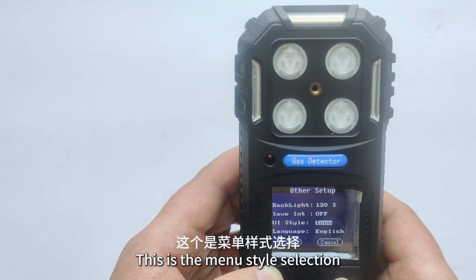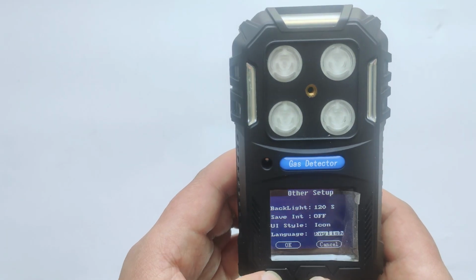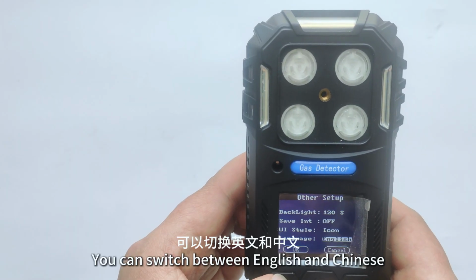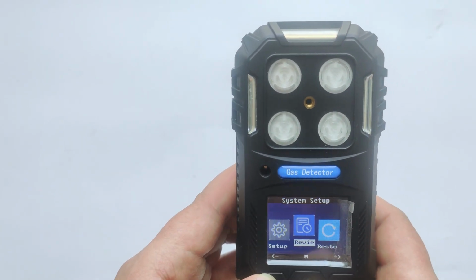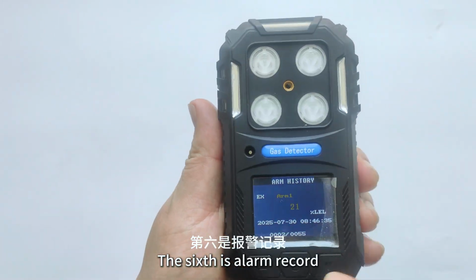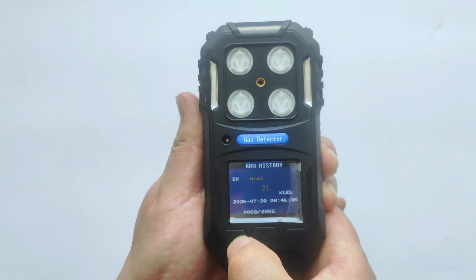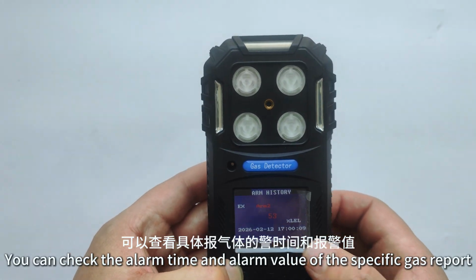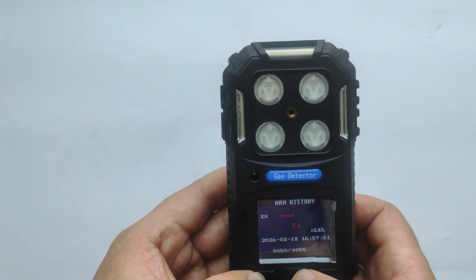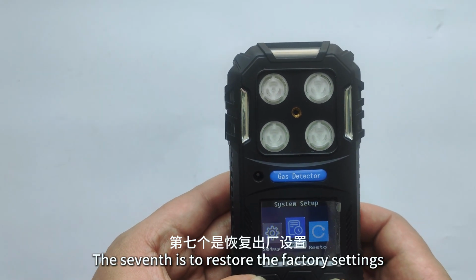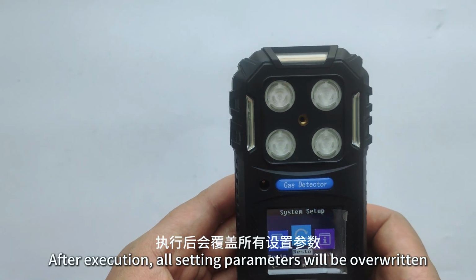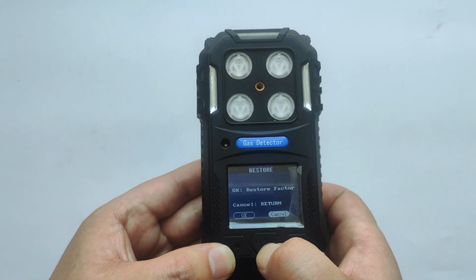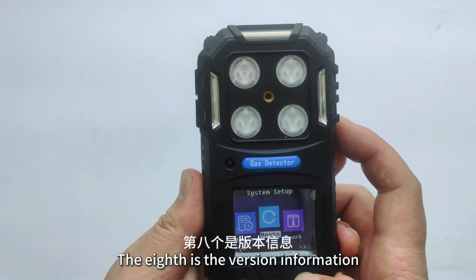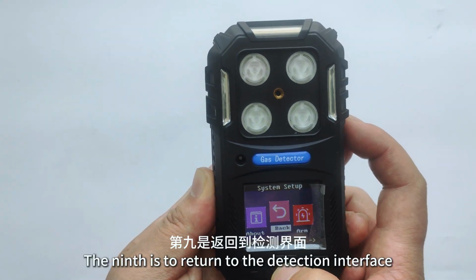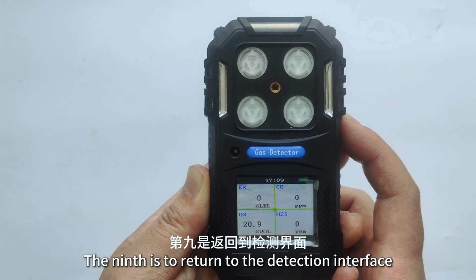This is the menu style selection. You can choose image mode or text mode. This is the language selection. You can switch between English and Chinese. Here's the graphical mode menu. The sixth is alarm record. You can check the alarm time and alarm value of the specific gas report. The seventh is to restore the factory settings. After execution, all setting parameters will be overwritten, including calibration parameters. The eighth is the version information. The ninth is to return to the detection interface.